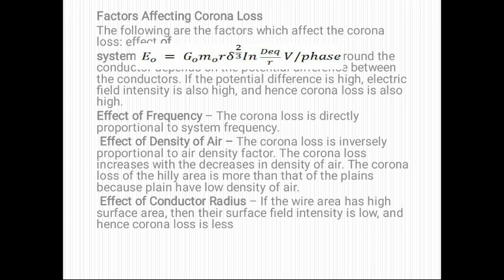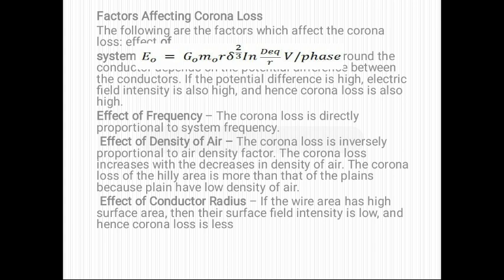Next is effect of conductor radius. If the wire area is high, then the surface field intensity is low and corona loss is also low. This is the phenomenon of corona effect, how it is caused, what the factors affecting corona are, what the disadvantages of corona are, and how we can minimize corona. Okay, now we revise shortly.